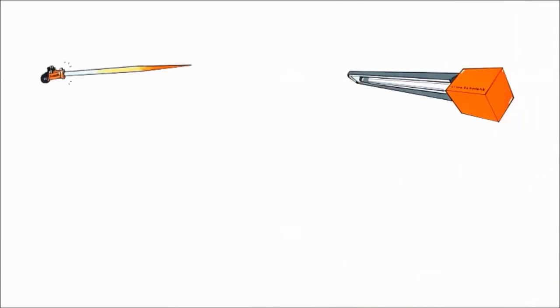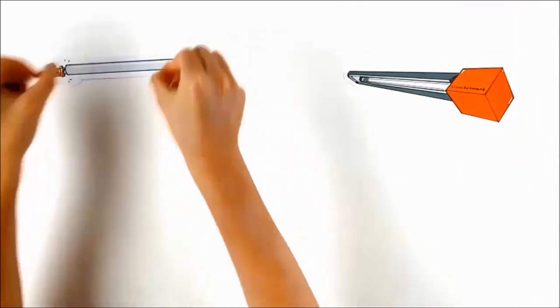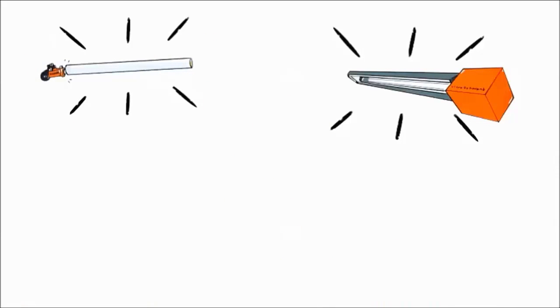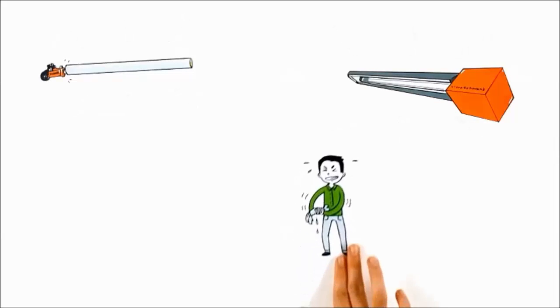With tube heaters, the combustion takes place in a tube. The tube then emits the radiation. Tube heaters work at lower temperatures, and therefore are usually more appropriate for buildings of under 4 metres height.